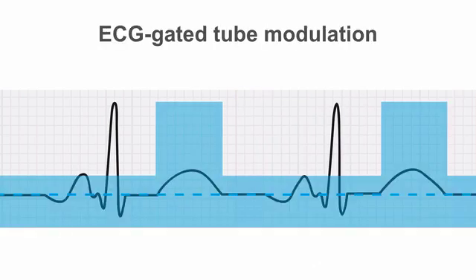In order to minimise the radiation dose from a full retrospective scan, we can employ a technique known as ECG gated tube modulation. This enables a reduction of the tube current at parts of the cardiac cycle which are less important or are not the point of interest. This keeps the radiation dose lower, but still more than a prospective scan. However, it can provide more data and a capability to perform cine imaging of the valves.